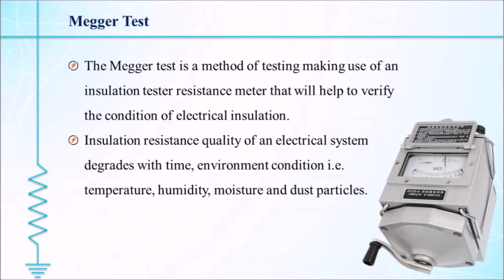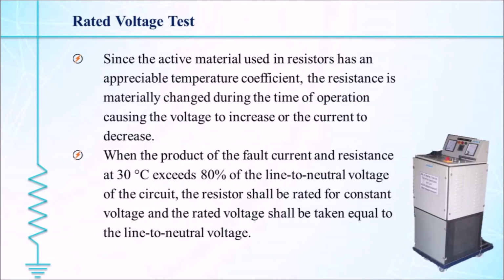Second test is the Megger test. The Megger test is performed for checking the insulation level of the device. In this test, high DC voltage is given between the terminal of the resistance and the enclosure. If the resistance is shown as infinity, then this test is successfully performed. If the resistance is low between the terminal and enclosure, then the chance of current flowing through the enclosure increases.